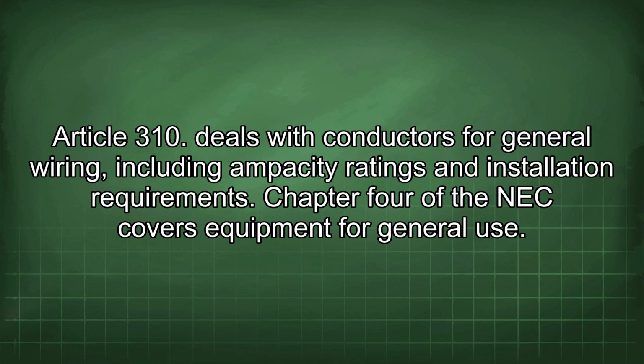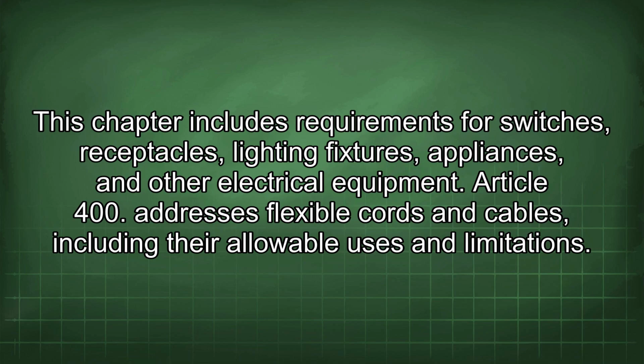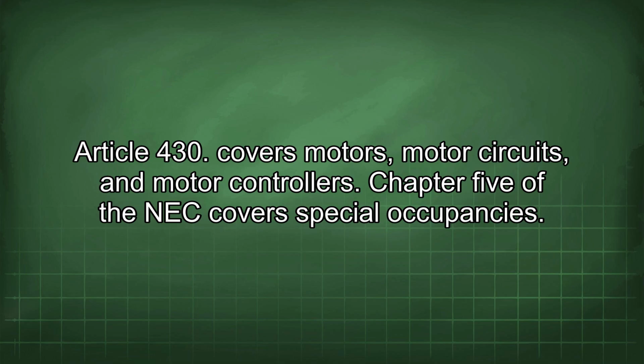Chapter 4 of the NEC covers equipment for general use. This chapter includes requirements for switches, receptacles, lighting fixtures, appliances, and other electrical equipment. Article 400 addresses flexible cords and cables, including their allowable uses and limitations. Article 430 covers motors, motor circuits, and motor controllers.